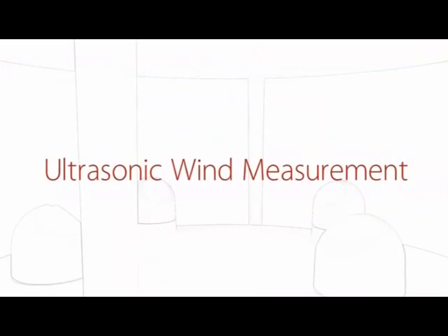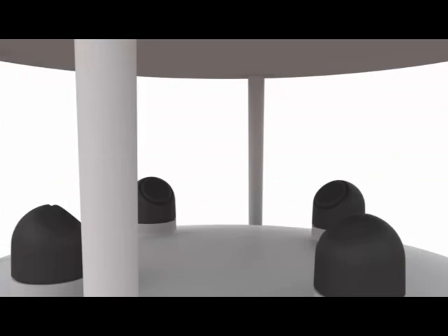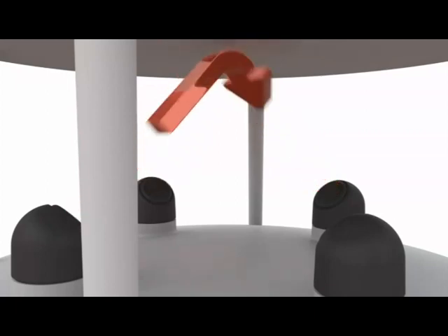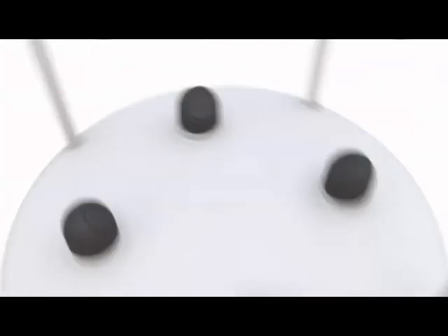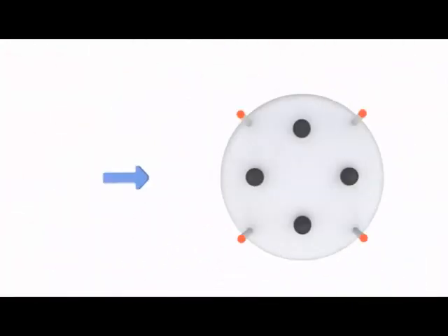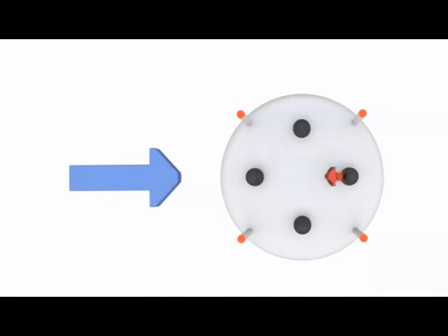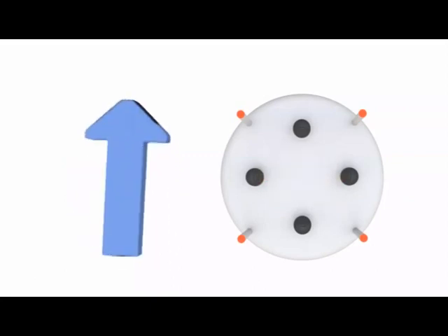Wind Sonic sensors use the ultrasonic time-of-flight principle to ascertain wind speed and direction. Opposing sets of transducers alternately send and receive ultrasonic pulses to each other. In still air these pulses travel at the same speed. The wind speed affects the send-receive pattern of the pulses — pulses in the direction of air movement will reach the opposing transducer more rapidly, whilst pulses into the wind will be delayed. The stronger the prevailing wind, the more prominent the effect will be.